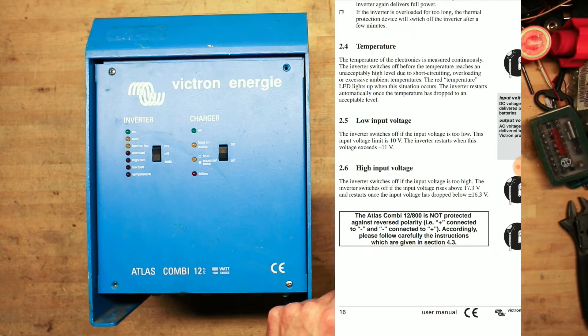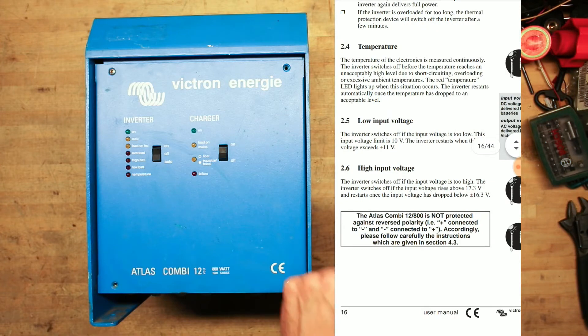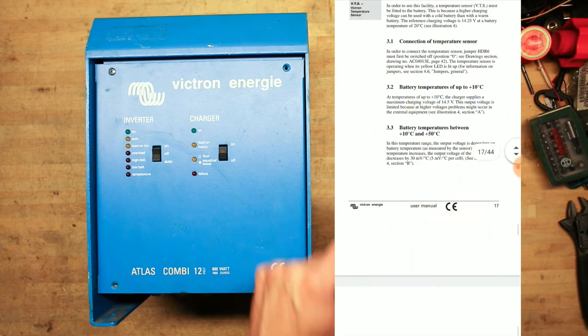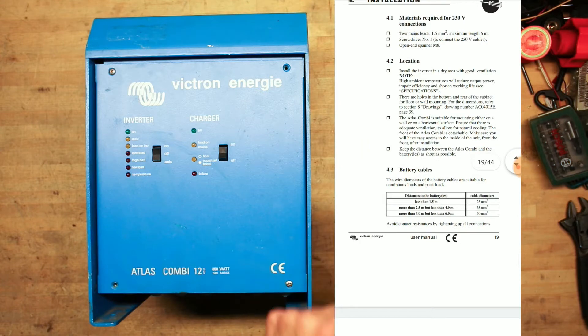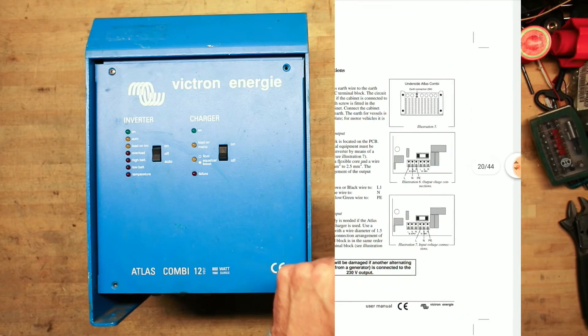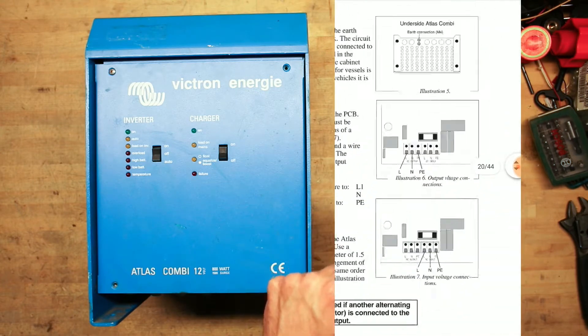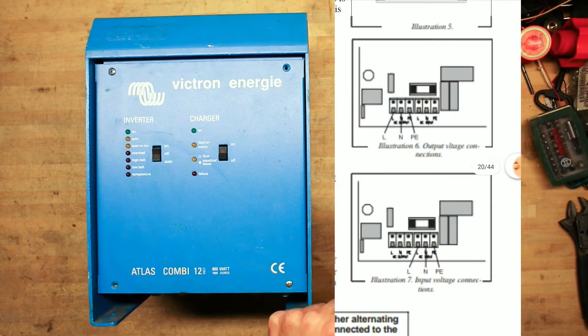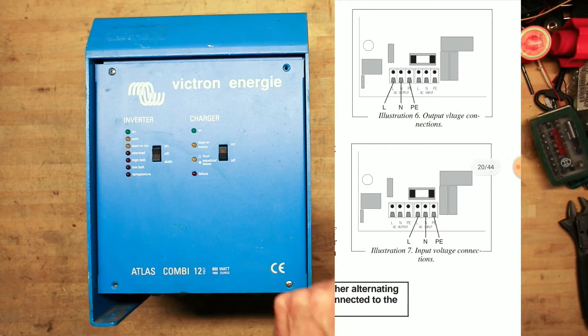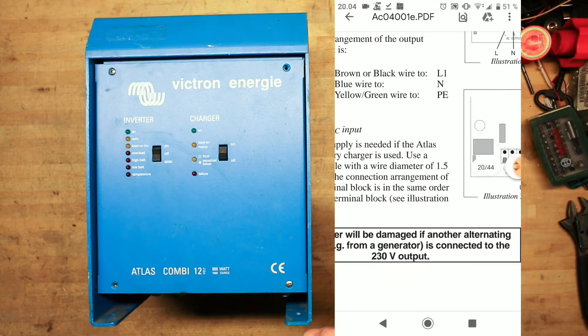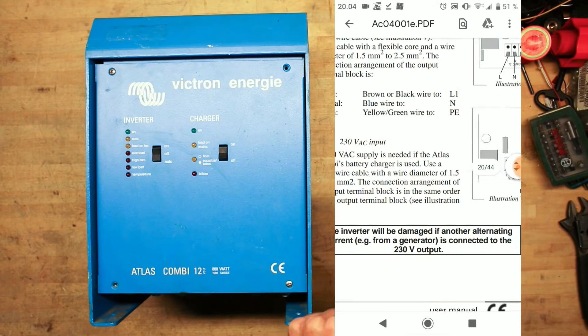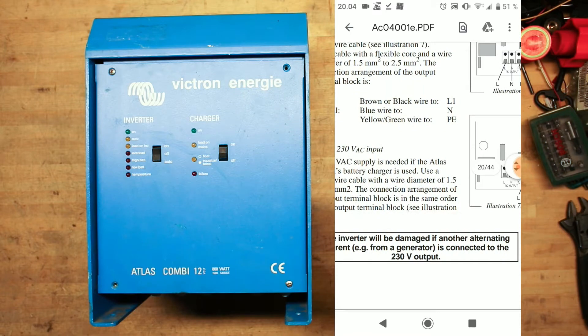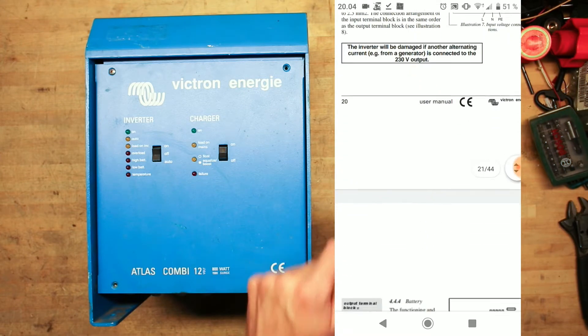It's not protected against reverse polarity. That's pretty important. Here are the connections. Output voltage connections to the left. Input voltage connections to the right. The inverter will be damaged if another alternating current is connected to the 230 volt AC output. So let's not do that.